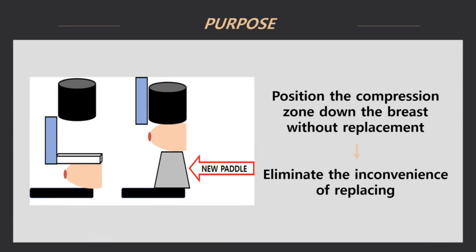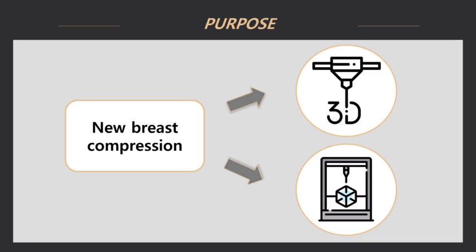Currently, spot compression uses a method of applying pressure from the top after changing the basic pressure paddle from the conventional filming method to the spot pressure paddle. The new method proposed in this study is not to replace the compression paddle as before, but to place the partial pressure paddle below the region of interest and then press it down with the basic compression paddle above. If the overall shape and surface of the compression rod are not uniform during 3D printing, images can be mistaken for tumors due to artifacts. This point should be designed with a flat, even density.